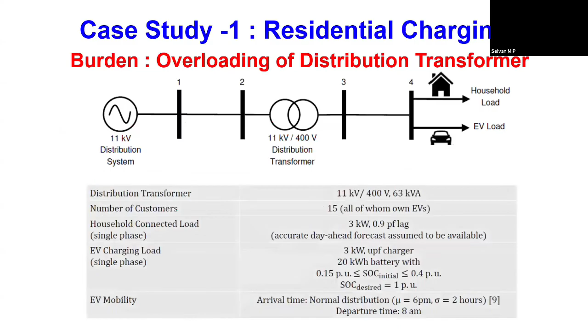We have taken a 4-bus system, along with household and EV loads. You can see here there is overloading of the transformer; transformer capacity is 63 kVA. So in a short period of time, from about 5:30 p.m. to 8 p.m., there is overloading of the transformer. Sustained overloading will reduce the life of the transformer, or during this period we may expect interruption of power due to a blown fuse.